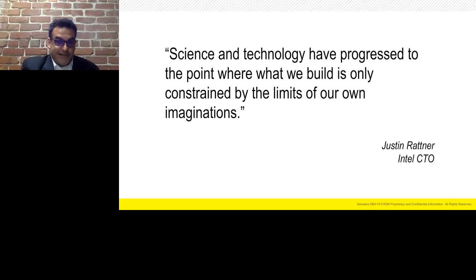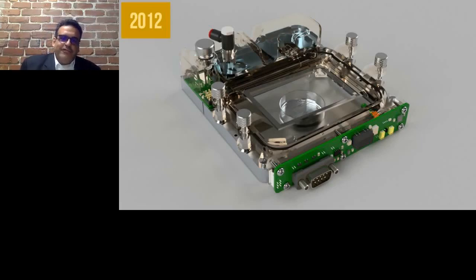So I took it upon myself to get rid of the metal. Can we make an incubator that didn't rely on metal? The reason we have metal in incubators is that we're relying on passive thermal conductivity. In these designs there's a relatively high concentrated heat source, that thin film heater, and we want to spread that heat evenly around and control temperature fluctuations. So there are lots of good reasons to leave metal in there.